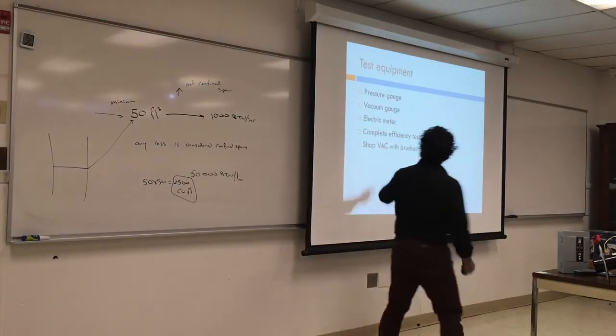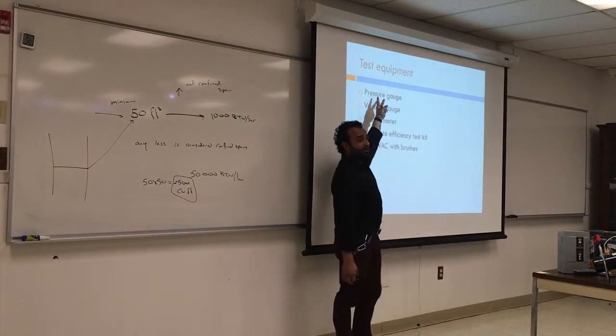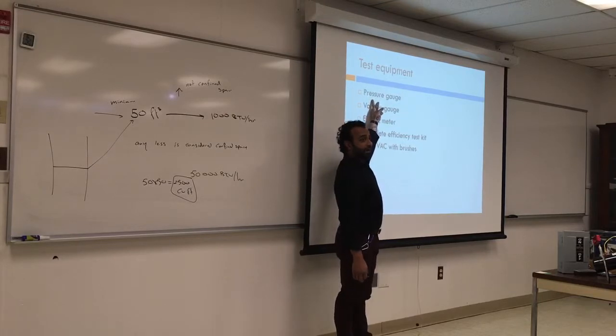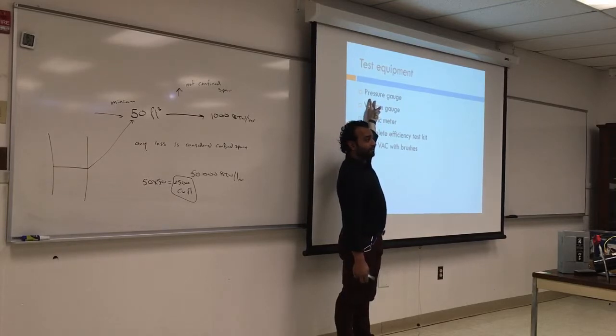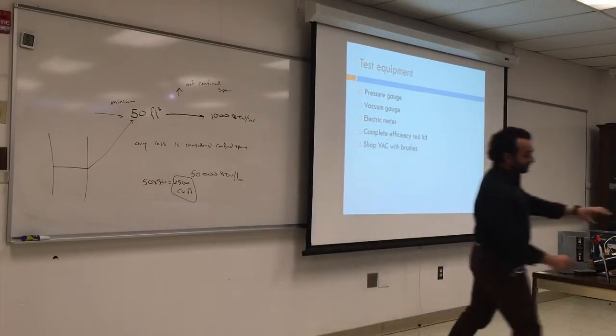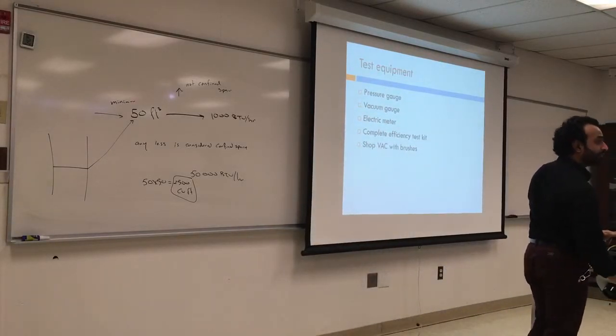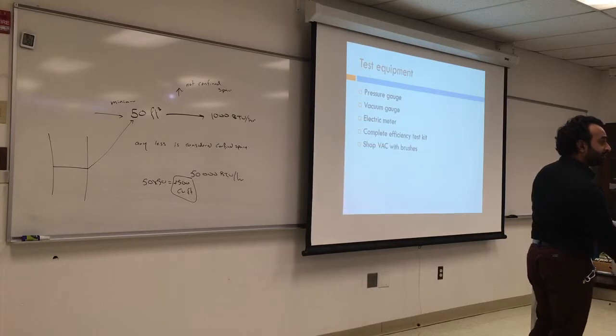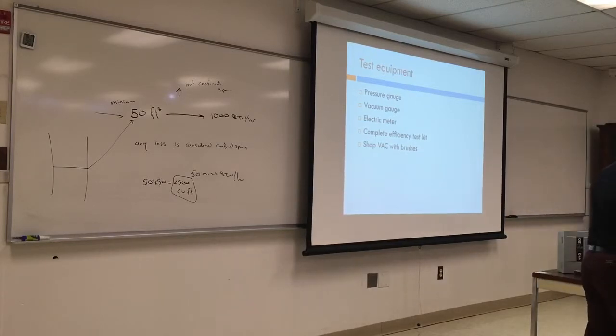Test equipment, pressure gauge. We use the pressure gauge, right? We know how they work. Where do you use a pressure gauge? Check pressure. Where? Oil burner. Where do you put it? At the outlet of the pump. So you're going to take this nozzle line out and put your pressure gauge.